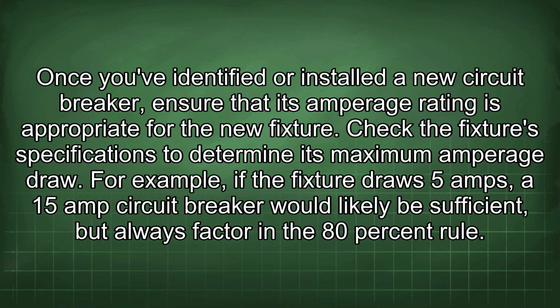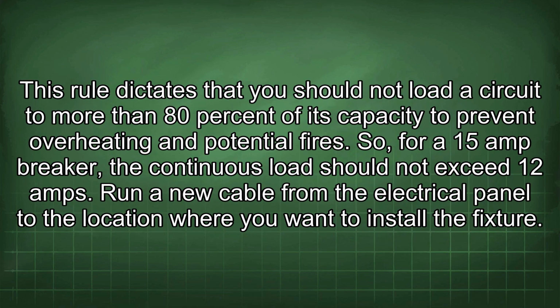Once you've identified or installed a new circuit breaker, ensure that its amperage rating is appropriate for the new fixture. Check the fixture's specifications to determine its maximum amperage draw. For example, if the fixture draws 5 amps, a 15 amp circuit breaker would likely be sufficient, but always factor in the 80% rule. This rule dictates that you should not load a circuit to more than 80% of its capacity to prevent overheating and potential fires. So, for a 15 amp breaker, the continuous load should not exceed 12 amps.